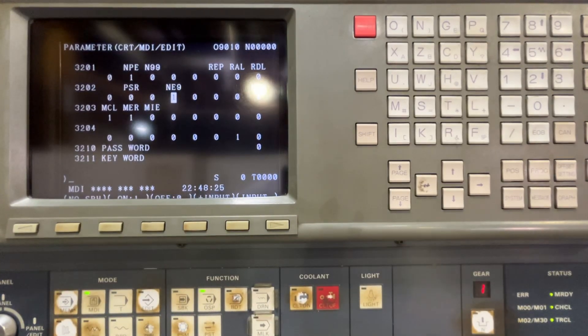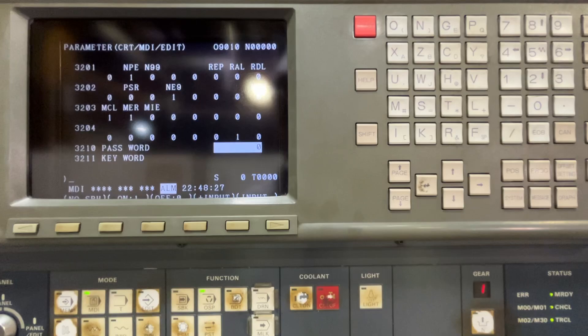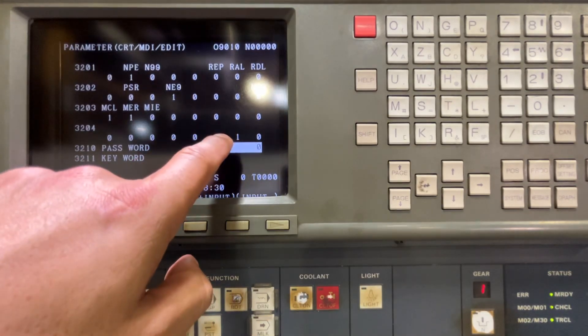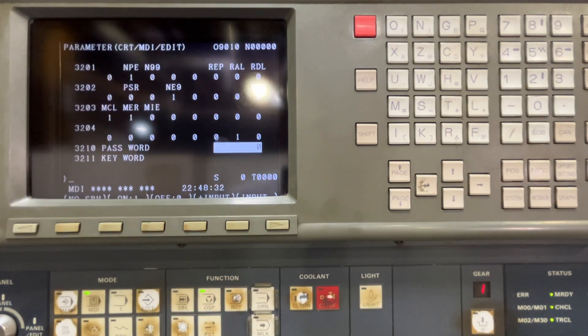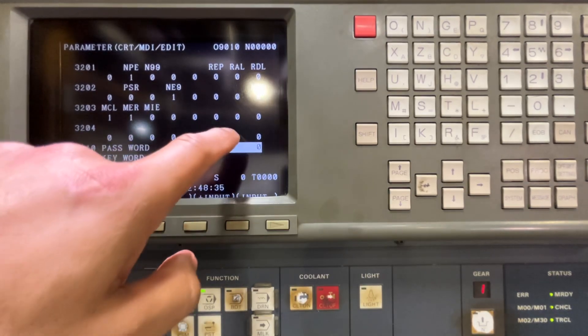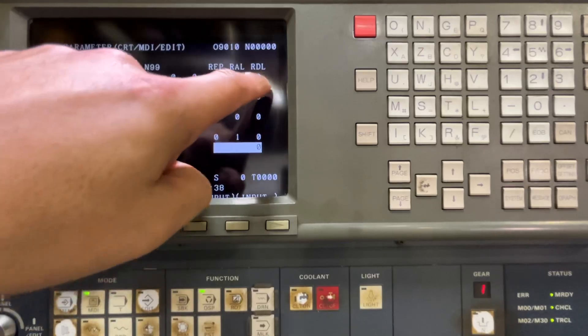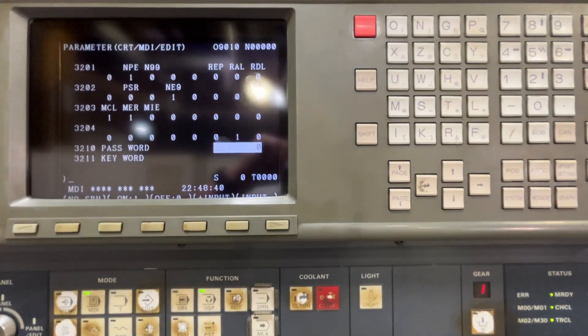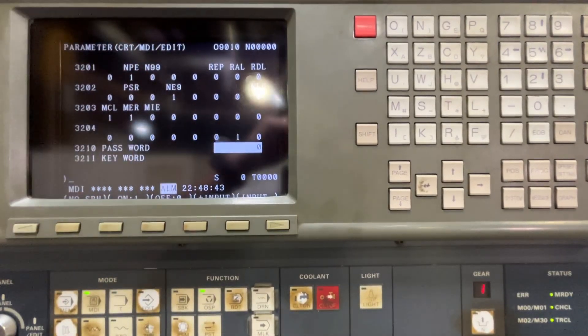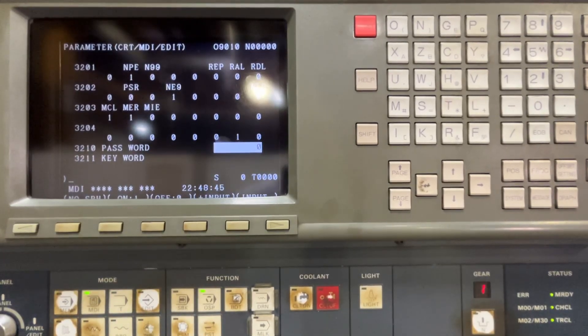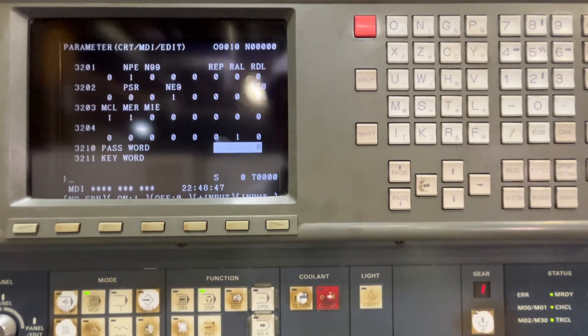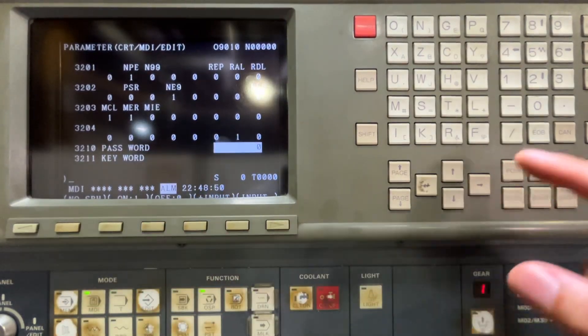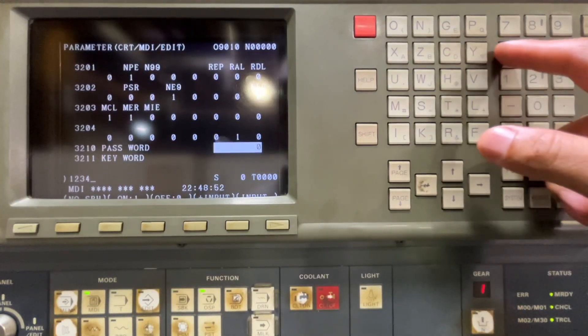Okay. And now if I set a password here, what I'm going to do is protect modifying these parameters. So this one will allow you to protect programs in the range of 8000 to 8999. So let's set a password, 1234 for example. Input.